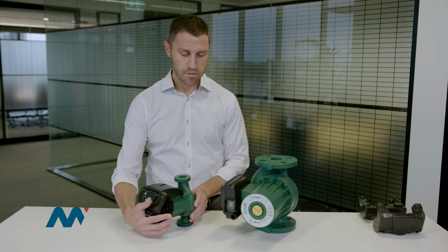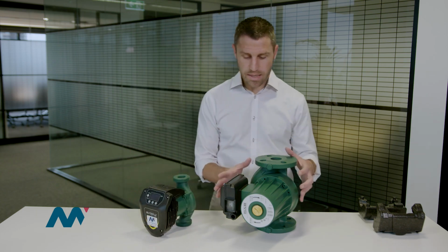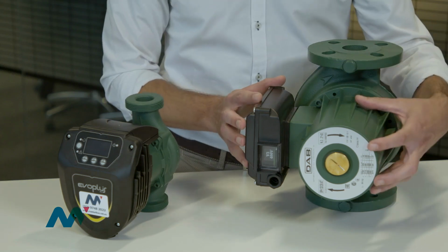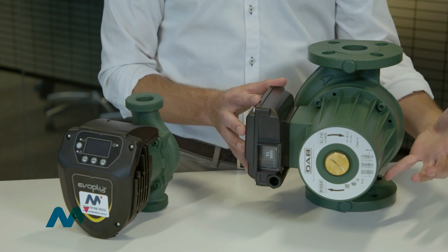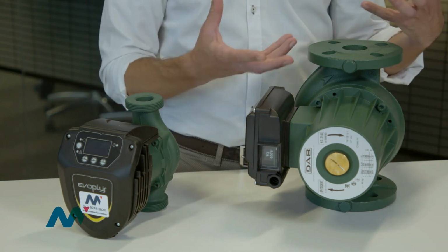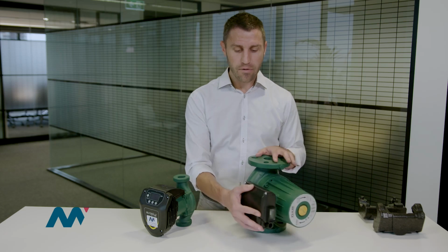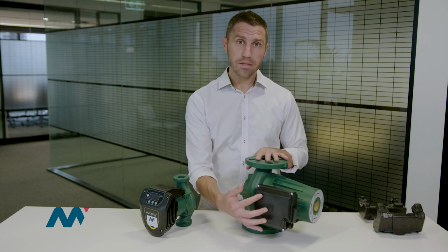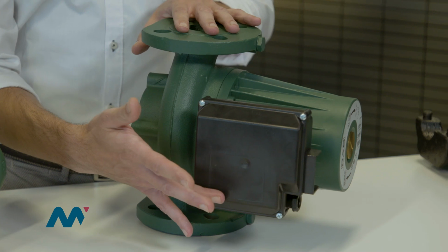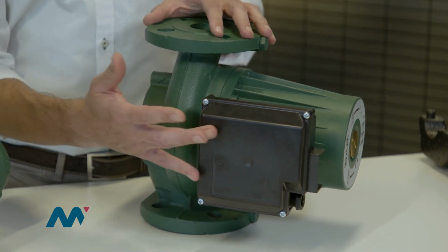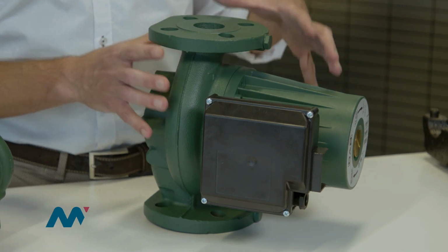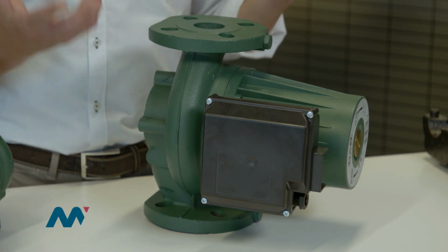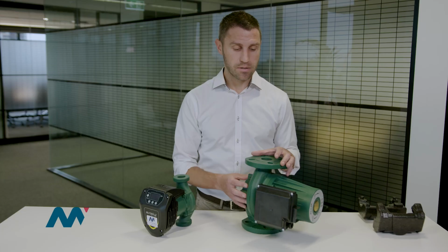with the pump. Okay? So in this case, we have an asynchronous motor that is a normal type of electric motor with copper winding, and here we have a speed selector. Speed number 1, speed number 2, speed number 3. That means that you can ask the same pump to cover 3 different curves of performance.